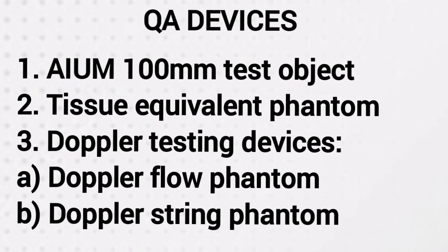The devices that are used in an ultrasound quality assurance program can be classified into two broad groups. The first is devices used by the sonologist or the sonographer. The second group is devices used by the service personnel. The commercially available devices used by the sonologist or sonographer to test imaging performance, based on established criteria set by the AIUM 94, 95, 96, are as follows: the AIUM 100 mm test object, the tissue equivalent phantom, and a Doppler device, which includes a Doppler flow phantom and a Doppler string phantom.